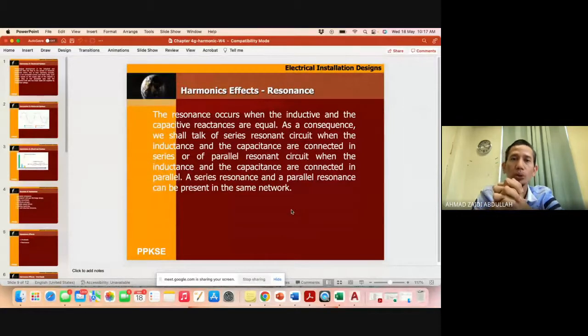As a consequence, we shall talk about series. Series resonance occurs when the inductor and capacitor are connected in series or parallel. We will see how the series and parallel connections work later. Series resonance and parallel resonance can be present in the same network. I need to share this because you will use the parallel or series connection for your power factor correction. Then at least you know why we need to install the power factor correction connection like this.